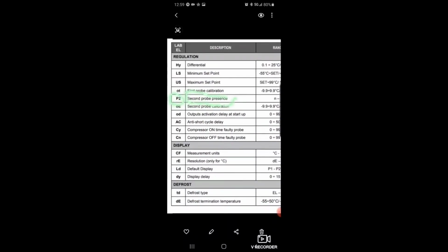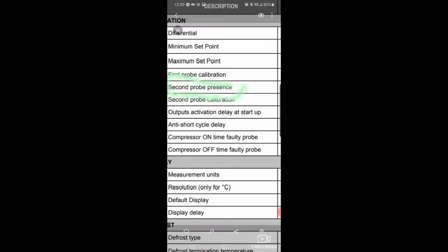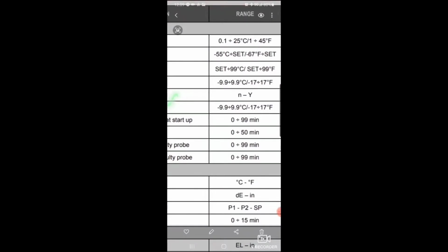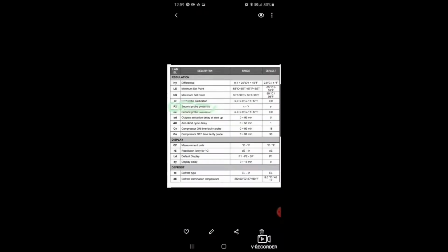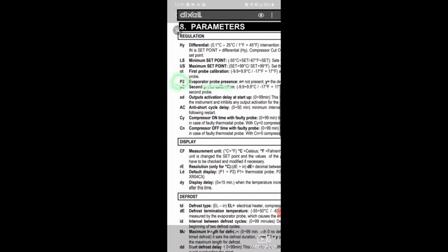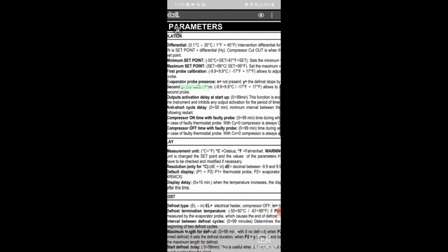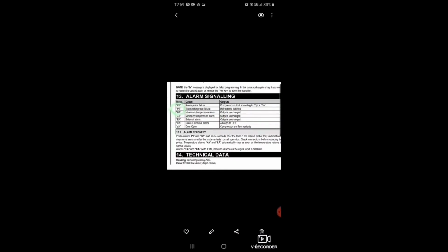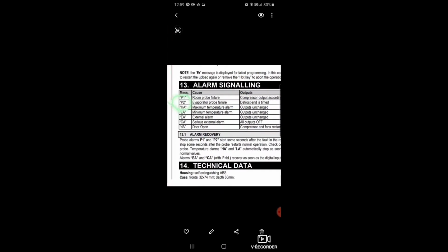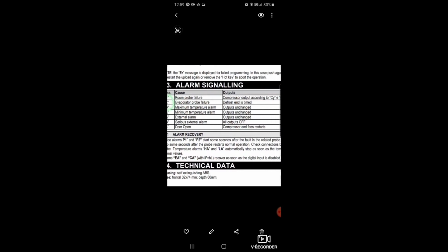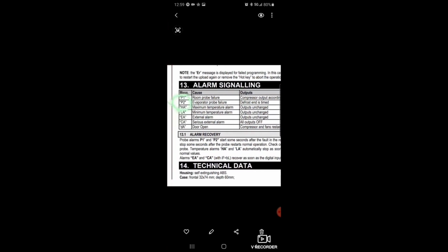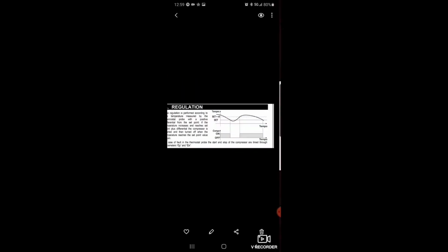Alright, so just a quick look at the Dixell PDF form. On this one, P2 error code description is saying second probe presence, range N and Y, default at Y. So here's another page. P2 evaporator probe present. So there's an N and Y. N represents not present. Y, the defrost stops by temperature. So here's another slide. P2 alarm signaling evaporator probe failure. Outputs defrost end is timed. So it's like a sensor for the defrost basically. And then here's one more.